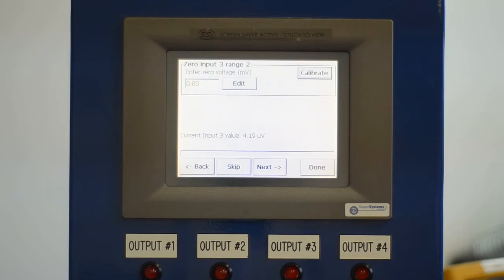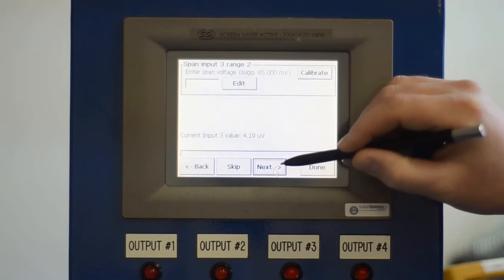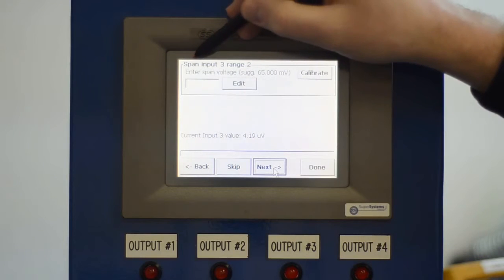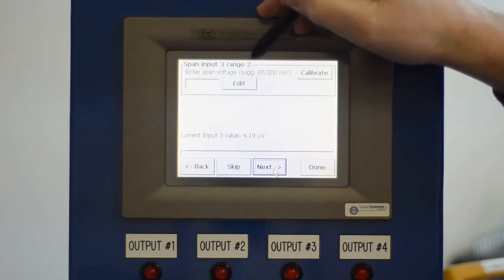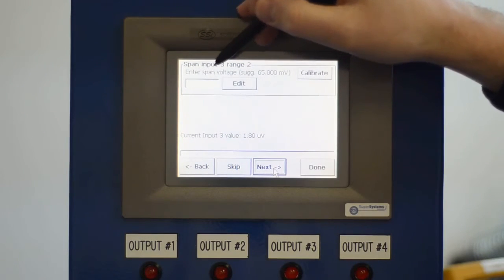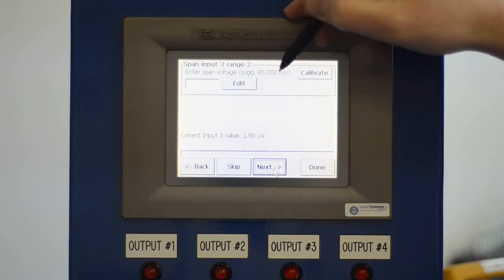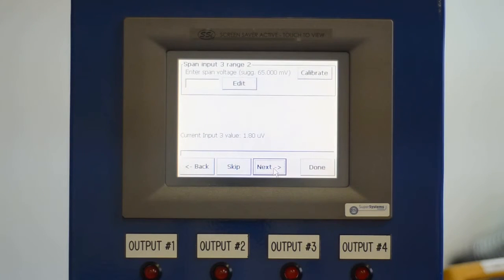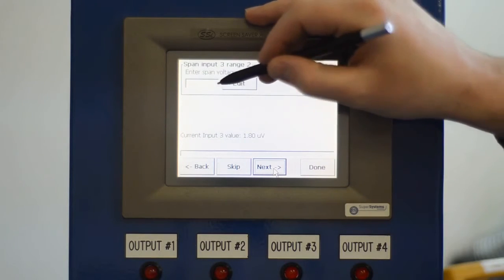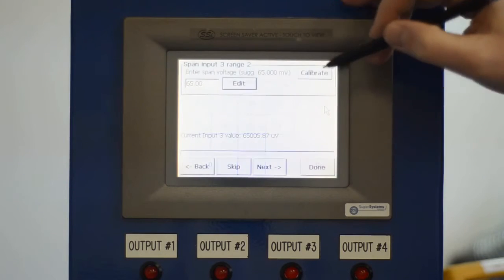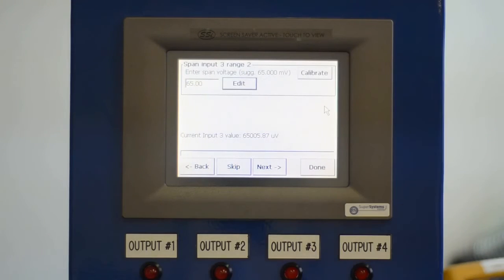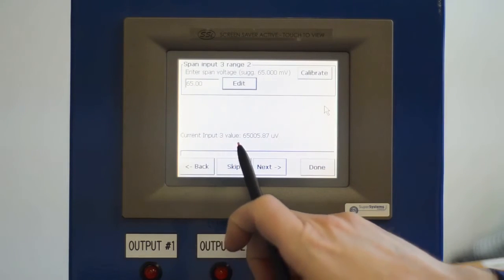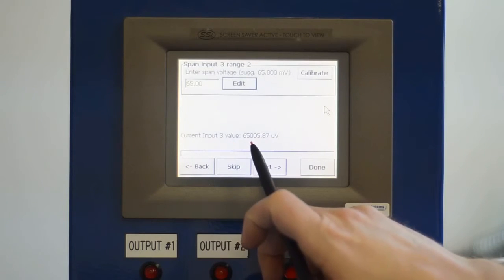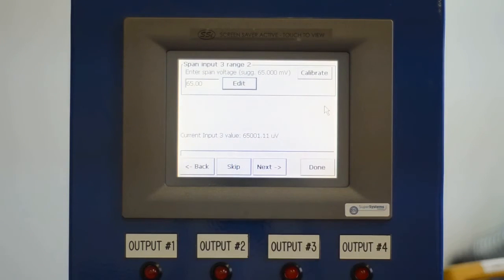Once the 0 calibration is complete, we're going to select next, and this is now going to allow us to span input 3, range 2. It's telling us a suggested span voltage of 65 millivolts, so I'm going to have my meter source in 65 millivolts. I'm going to select edit to edit this field, let it know that I'm sourcing in 65 millivolts. And as you can see, it's showing us here the current input 3 value now is 65,000 microvolts.